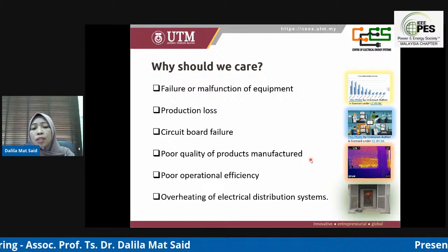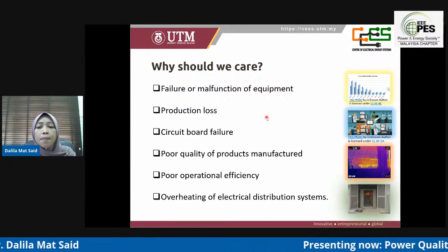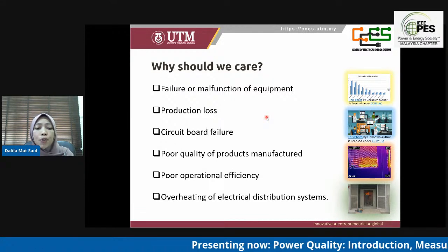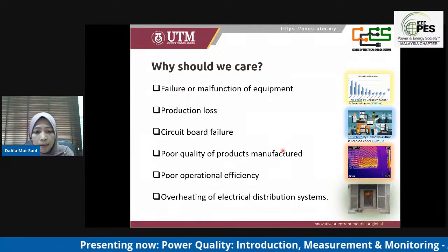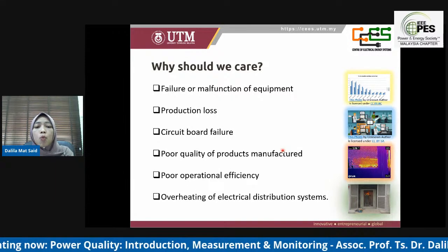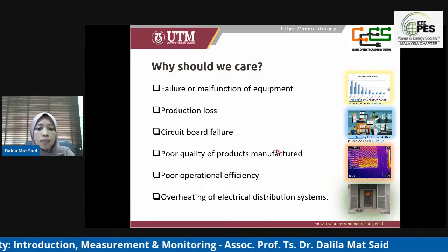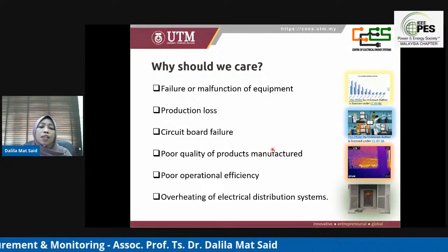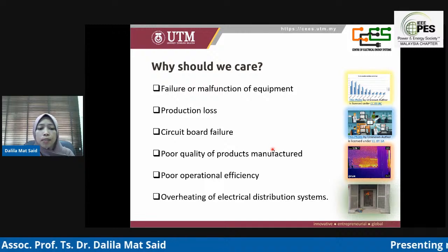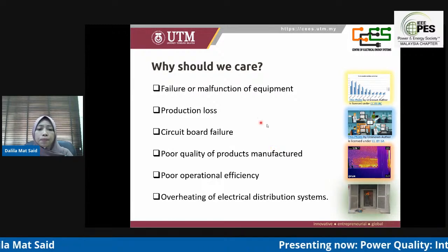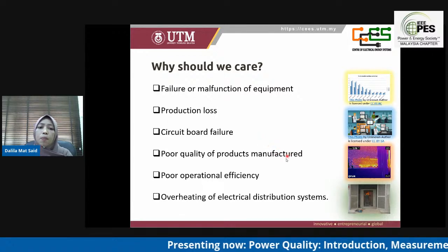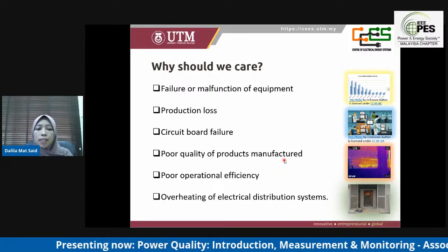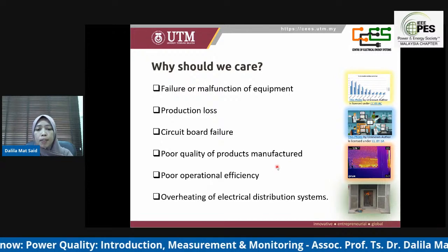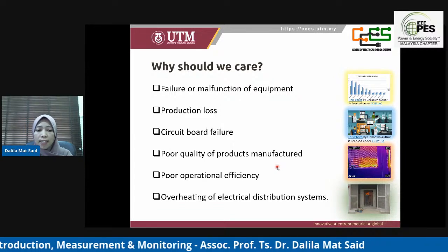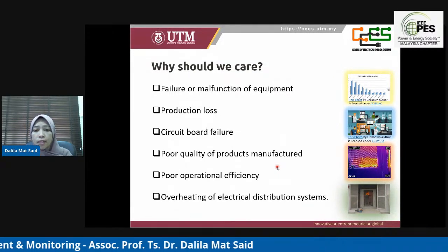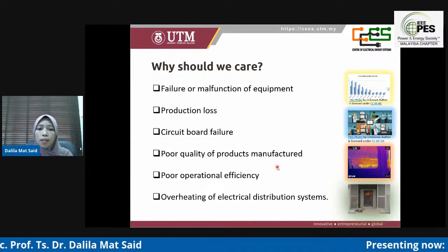Interruption can damage a partially complete product, causing the material to be rerun or scrapped, and electronic cards fail. Among the impacts arising from harmonics, condensers within the interference filter circuit board at the card entrance may draw excessive current and explode due to harmonics, and they may lead to poor production, poor quality of production, and poor operational efficiency. Harmonic in the transformer will also increase the heat and insulation problem with losses. Overheating is also one of the negative results of harmonic source skin effect on conductors.